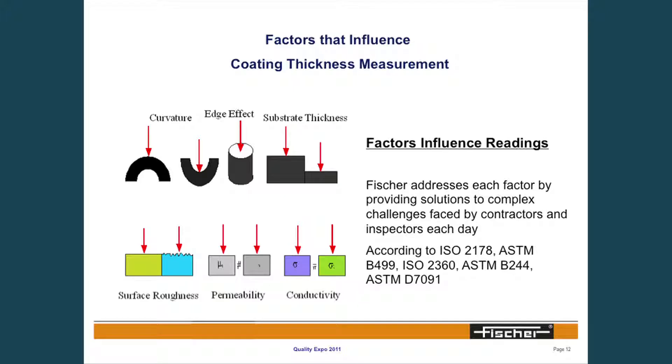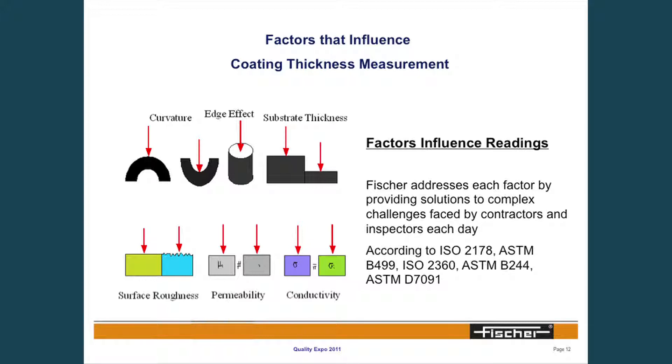There are things that influence film thickness measurement. This is an example that ASTM uses of those factors: curvature, how close we're measuring to an edge, substrate thickness, and conductivity can all influence readings if we don't have an instrument that compensates for that, or if the probe isn't optimized for those specific part geometries. A lot of times people will have a probe capable of measuring on a curved surface, but it might not be the most ideal probe for that particular diameter or curvature. Looking deeper at probe specifications can help us achieve the goal of reducing material costs.